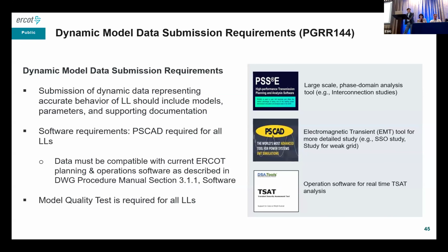TSAT is being used by our system operations for real-time TSAT analysis. PSSE is the traditional dynamic stability analysis tool used in the connection study. PSCAD provides very high fidelity EMT analysis that can capture sub-cycle phenomena that cannot be evaluated in PSSE or TSAT. And the model quality test has to be done using all three software. That provides a very important cross-model validation step.